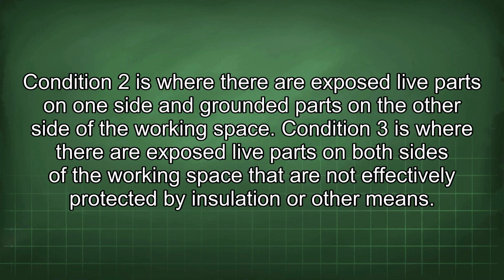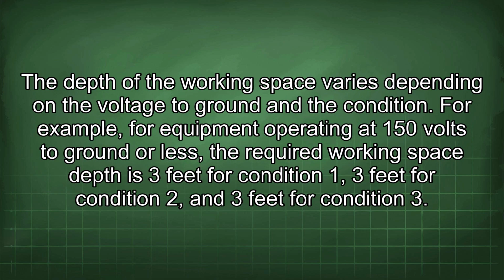Condition 2 is where there are exposed live parts on one side and grounded parts on the other side of the working space. Condition 3 is where there are exposed live parts on both sides of the working space that are not effectively protected by insulation or other means. The depth of the working space varies depending on the voltage to ground and the condition.